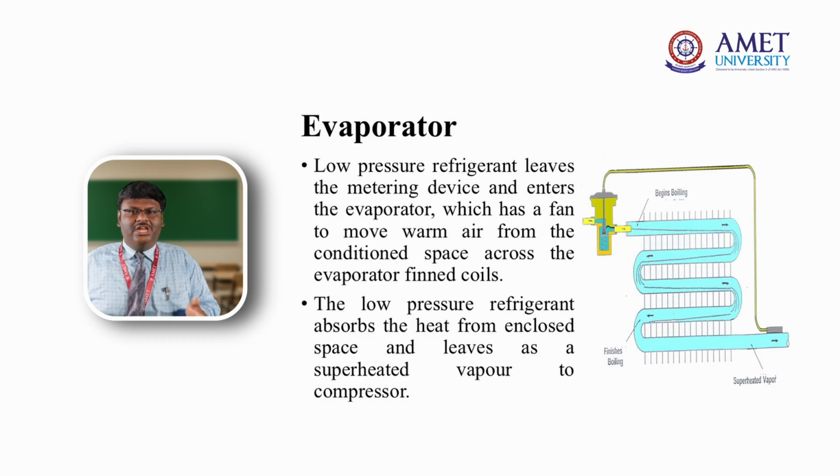Say initially the room is at 28 degrees, and refrigerant passes through the coil at 8 degrees. The air present in the room will touch the coil. Obviously, energy will get transferred from the room air, which is at 28 degrees Celsius, to the refrigerant flowing inside the coil at 8 degrees. As a result, the room temperature reduces; we get a cooling effect in the evaporator region due to the low temperature, low pressure refrigerant flowing across the evaporator.